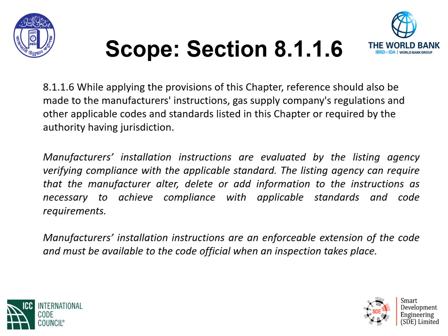So the manufacturer's installation instructions are an enforceable extension of the code and must be available to the code official when an inspection takes place. They are key to having requirements on site as to how the appliance needs to be installed, set up, and even started up.